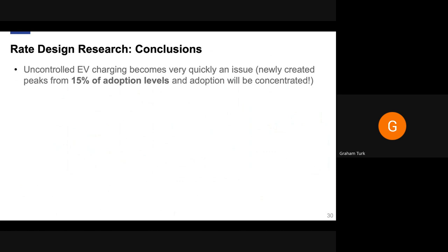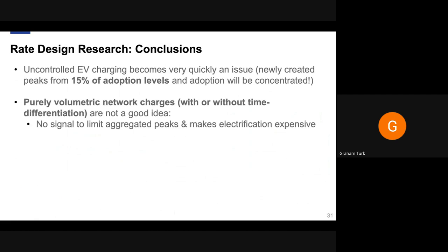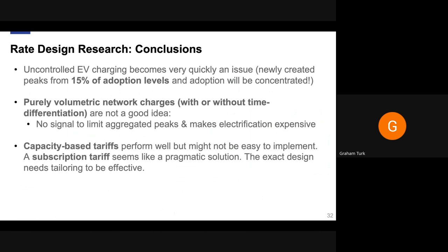A few conclusions from our modeling — using surveys to generate synthetic load profiles: you don't need to reach very high EV adoption before this becomes a big issue, especially where EV adoption is concentrated. The rates that utilities are starting to offer to incentivize EV charging are really not well-suited for loads like EVs that can be highly correlated and scheduled without customers doing anything beyond setting up an app or website once and never touching it again. We tested a bunch of capacity-style tariffs and there's definitely a balance between complexity for the customer versus efficiency if they behaved perfectly. Looking toward rates used in Spain and France that have worked well to help customers manage demand and avoid distribution expansion is promising.